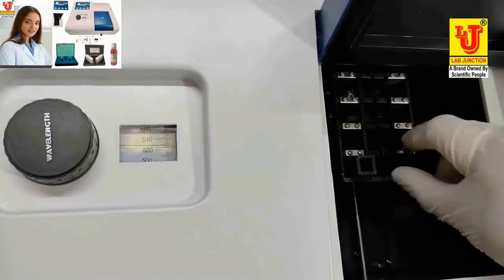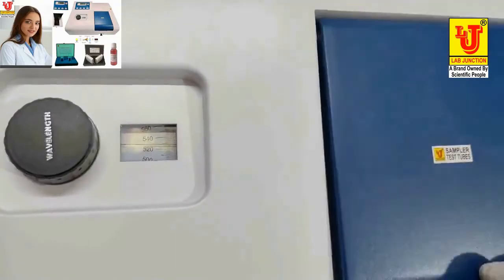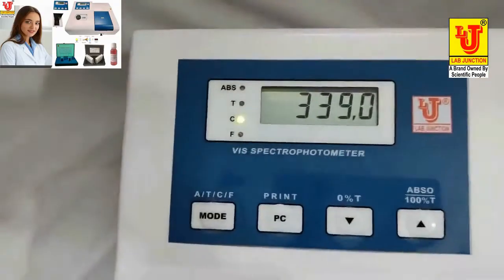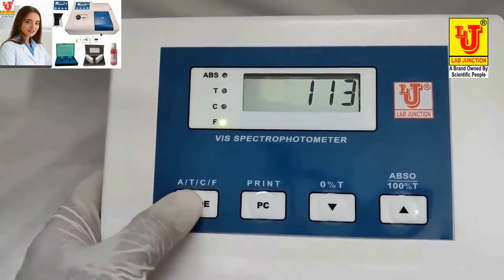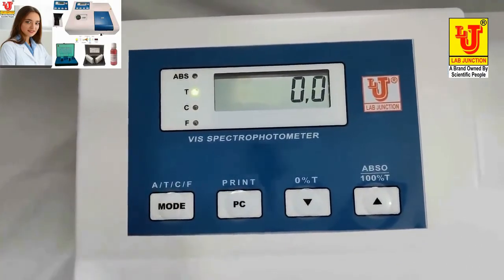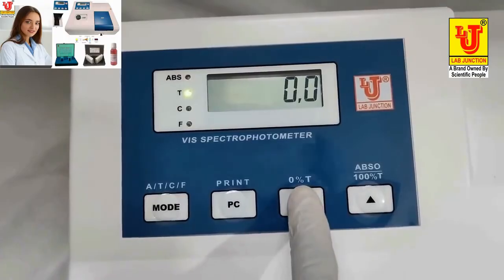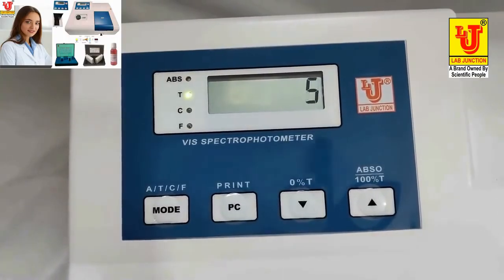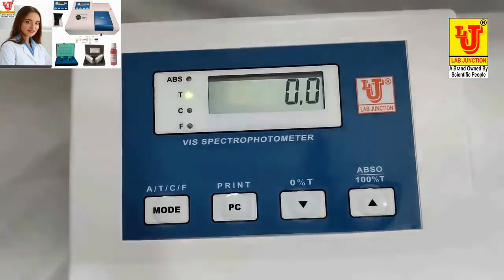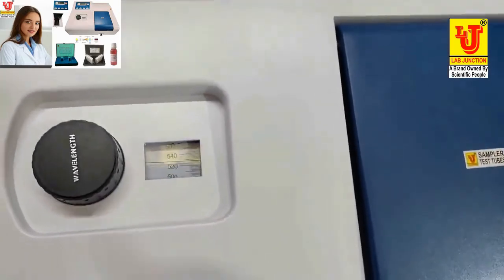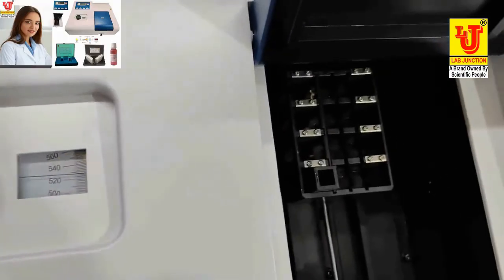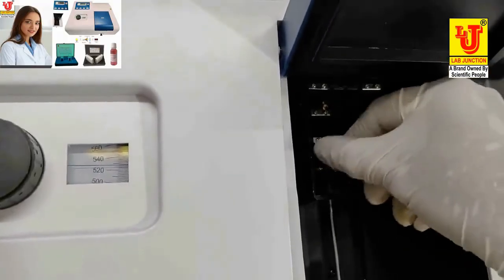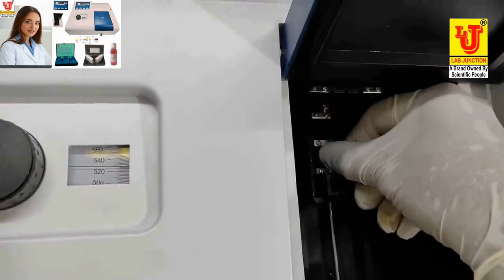On position 1, dummy is there. Go to transmission mode. Press 0% transmission for preset 0 or dark current, like this way. Now I am removing this jack.